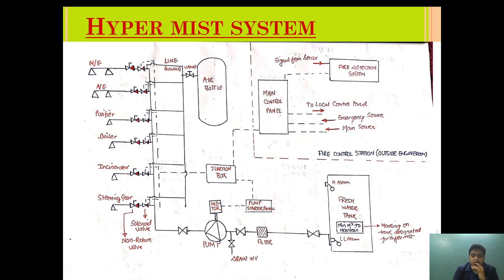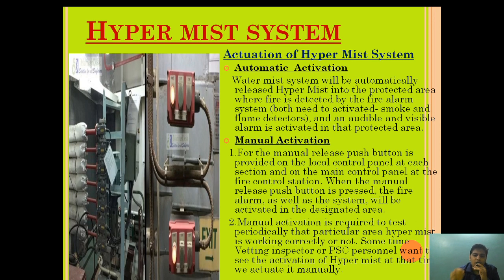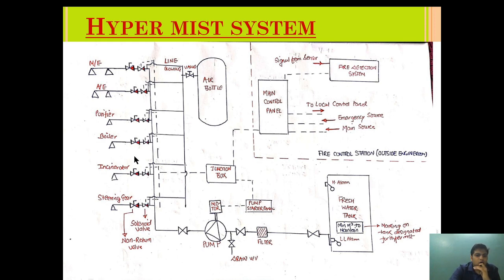Once the signal comes to the main control panel, it processes the signal and sends it to the junction box, opening the solenoid valve for the affected area and also starting the pump automatically. So the signal from the sensors does two things: it activates the solenoid valve and starts the pump. For manual release, a push button is provided at the local control panel at each section, and also at the main control panel at the fire control station. When the manual push button is pressed, the fire alarm and system are activated in the designated area.